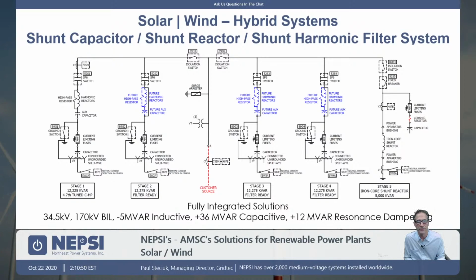And what you'll find if you talk to any studies engineer who's conducted harmonic studies on these wind farms and solar plants is that the results of the study are oftentimes inconclusive. You might have a harmonics problem, you might not. And this is a big issue with the harmonic studies that are conducted for these industries. It takes a little bit of study work to understand why this is the issue. But you have caps, you have the collector system, they cause resonance, you have low-level harmonics. And the question is, you do not really know exactly the system, so you cannot always exactly predict whether or not you have a resonance issue. And the other thing is that IEEE 519, the 2014 standard, is quite strict when it comes to renewable power plants. You're squished down to the first row in the distortion limits at the point of common coupling, so therefore it makes it difficult to meet the standard.